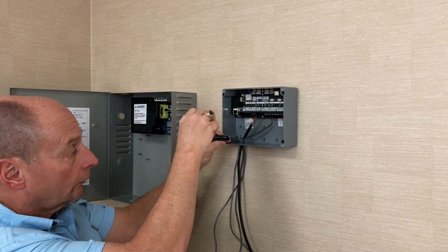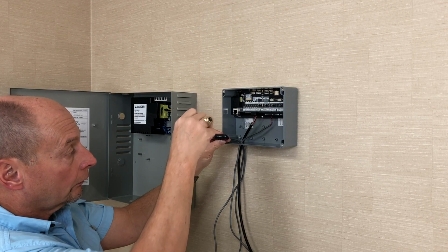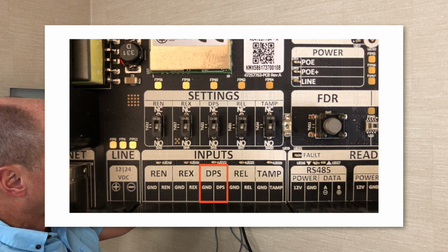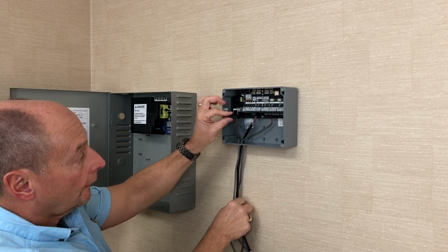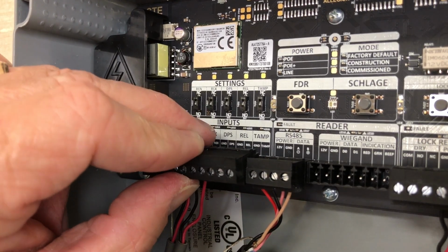Please note, relay output wiring must use a dedicated shielded cable. Do not run relay output wiring in the same cable as any other CTE wiring. See the user guide for more information. Next, connect any input switches to be used, such as request to exit and door position. Please note that there are only 2 connection points for each switch. Normally closed and normally open are handled by the selector switches above the inputs. Connect the 2 wires from each switch to the corresponding points on the inputs terminal.